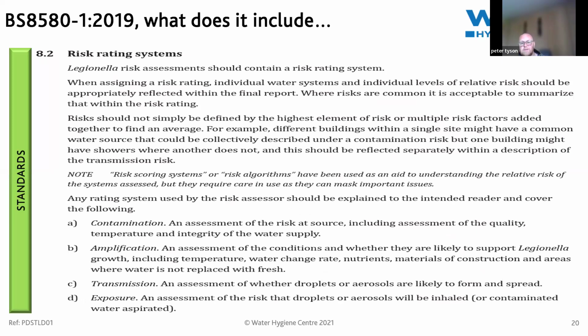Risk rating systems: L8 and British Standard 8580 don't detail a scoring method. The 8580 details the need for a scoring matrix to be defined and included in the risk assessment, and the risk should not just be defined by the highest risk issue. The risk matrix needs to consider contamination, amplification, transmission, exposure, growth, and aerosol exposure.